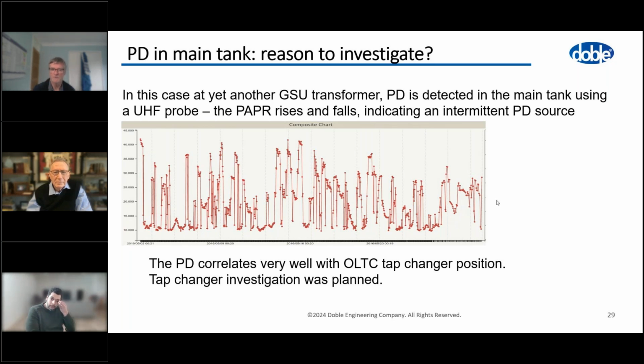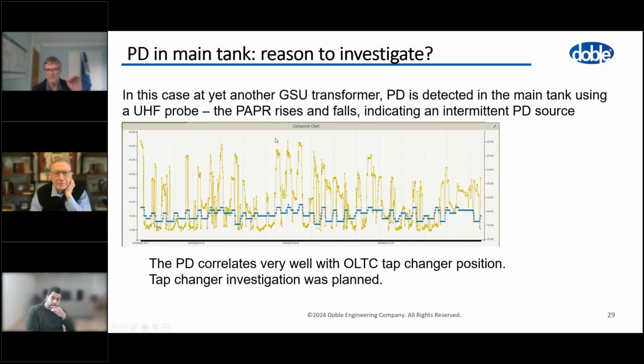If we could go down one, please. You see that this correlates, sorry, they changed color in the slide here. Gold is the partial discharge and the blue is tap position. And, Mark One Eyeball, you can see when the tap position rises, in general, the partial discharge rises with it, and when the tap position falls, PD comes down. That's a very strong indication that we need to be investigating the tap changer, which was planned. And so the technical decision was to go and investigate, see if we've got any loose contacts, see if we've got any worn away, if the spring has failed, and so on and so forth, a whole bunch of different possibilities.